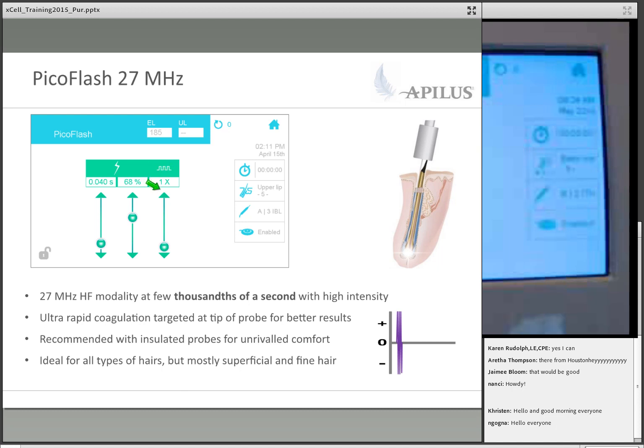The third thing that we see is our pulses. So when you see the little bumps, think pulses. And so we have it on 1 pulse right now, meaning that when I press on the foot pedal, it will just beep once. But I can change that, and the machine will give you as many as 9 pulses. So you can go up from there. On the right-hand side, remember I told you if you get lost, you want to just go home, you can click the home button and go back home. We have a timer, we have our presets, we have some fine-tuning with the probes, the type of insulation that we can put in, and this is our auto mode. We'll go through all of these independently.